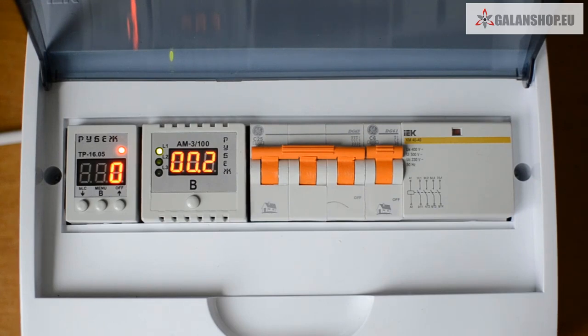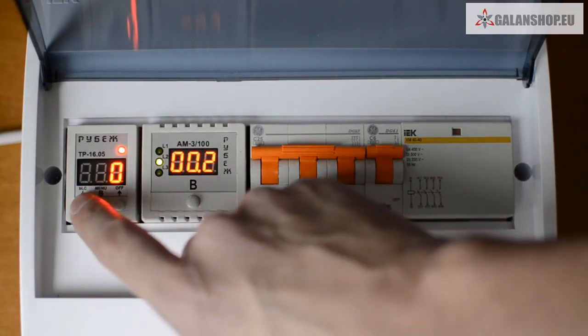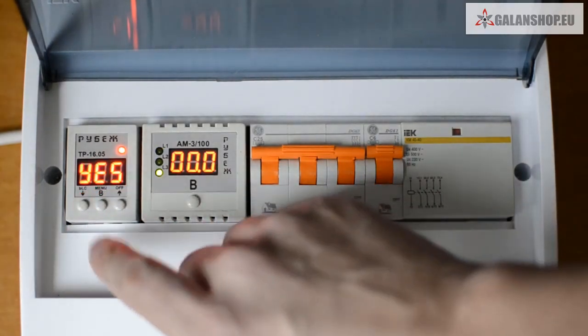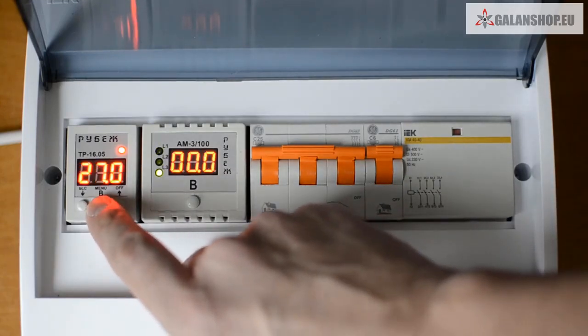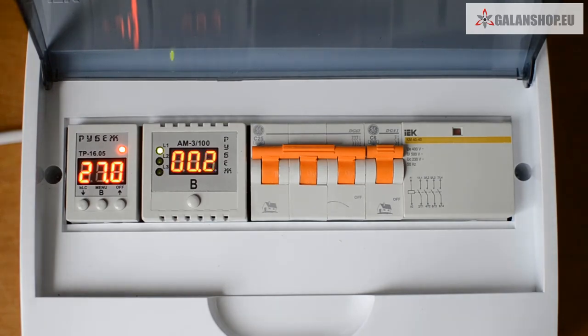The aim of this function is to calculate energy consumed over a certain period of time, for example, over a month. To check or reset the recorded time, you need to enter the heat controller's menu. In order to do it, press the B button and hold it for 2 seconds. Then press the same button shortly and choose a TRE submenu. After that, you can view the recorded time by pressing the up or down buttons. In order to reset the counter, use down or up buttons to select yes value and press the B button shortly to confirm your choice under the TRE menu.